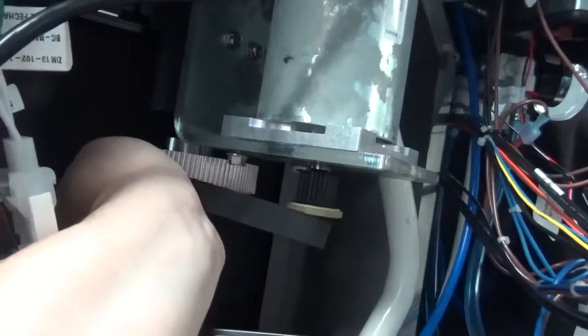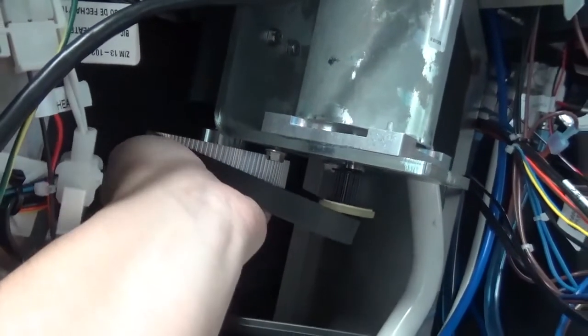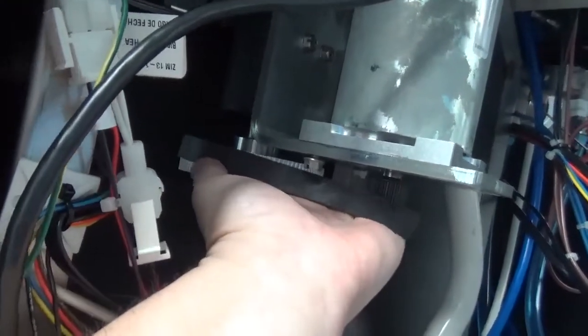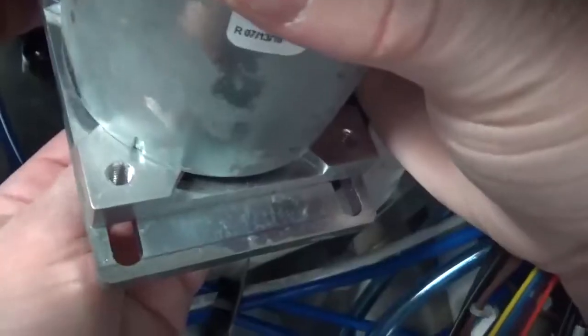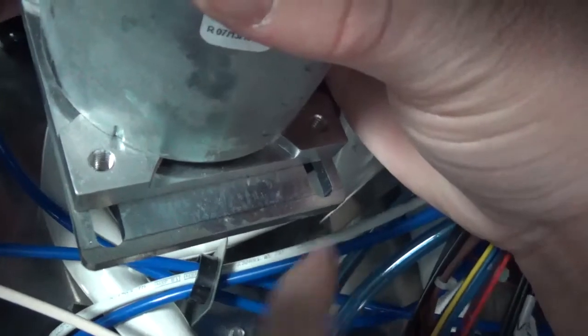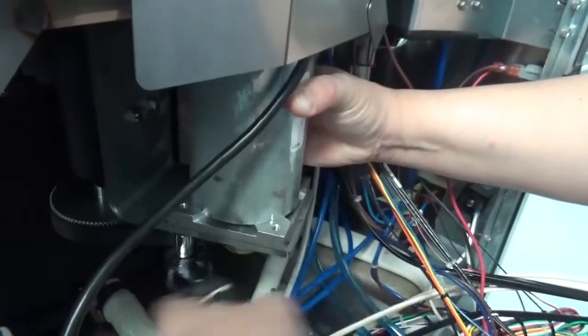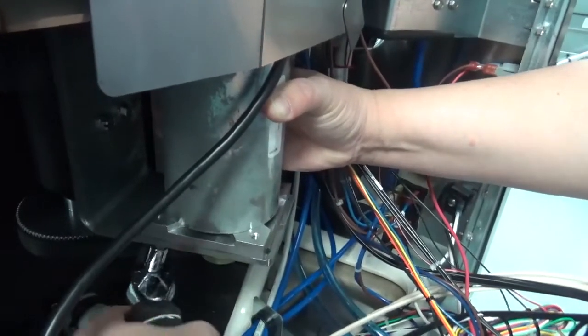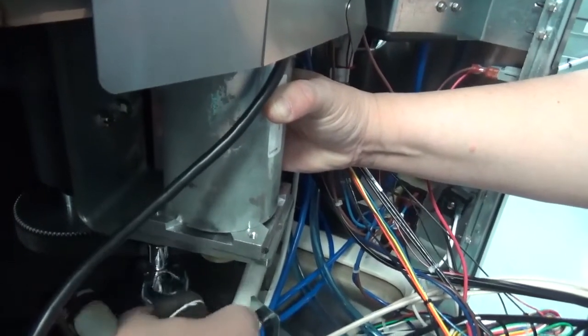Carefully remove the old ice shaver belt. Install the new ice shaver belt over the pillow block pulley and the ice shaver motor pulley. Locate the line marking the motor position on the mounting bracket and move the motor back into place. While holding the motor in position, tighten the two bolts to secure the motor to the motor mounting bracket.